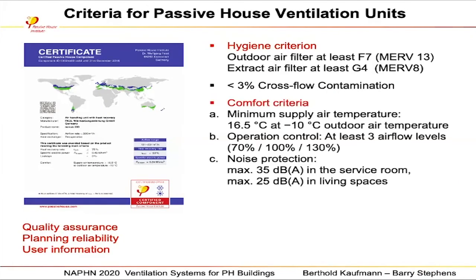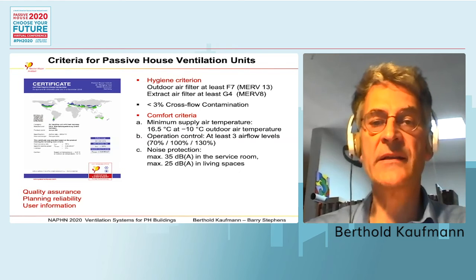requirements. First of all, the filters have to be good. Here are the filter class F7 for the European and the MERV 13 for the American context. So good filters for indoor air coming in, and the extract filters need not be of such good quality, but well, we need a filter just to keep the heat exchanger clean. Well, what is very important is there should be no cross flow between air coming in and air going out. So the air tightness must be good, so that there is no mixing of air coming in and going out.